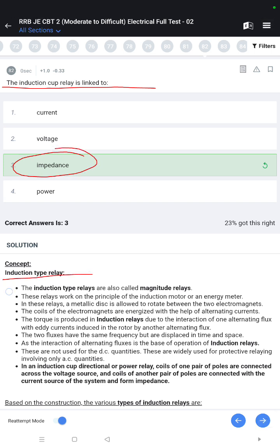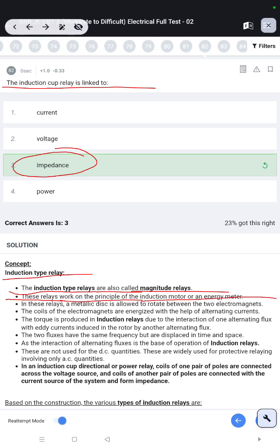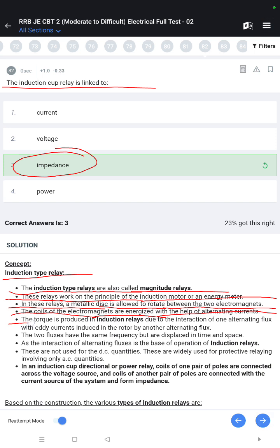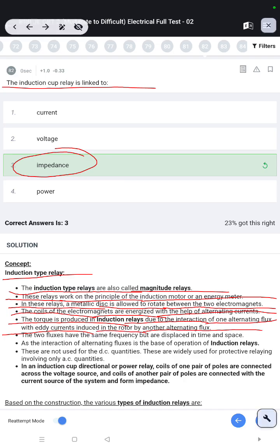The induction type relays are also called magnitude relays. These relays work on the principle of the induction motor or an energy meter. In this relay, a metallic disc is allowed to rotate between two electromagnets. The coils of the electromagnets are energized with the help of alternating currents. The torque is produced in an induction relay due to the interaction of one alternating flux with eddy currents induced in the rotor by another alternating flux. The two fluxes have the same frequency but are displaced in time and space.